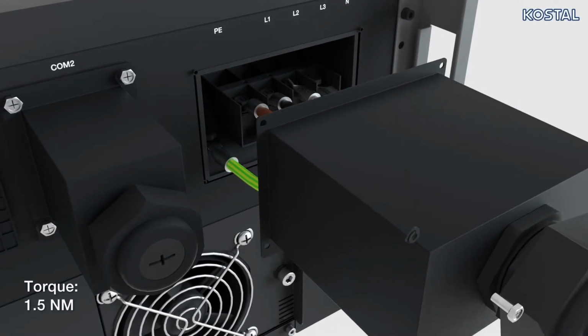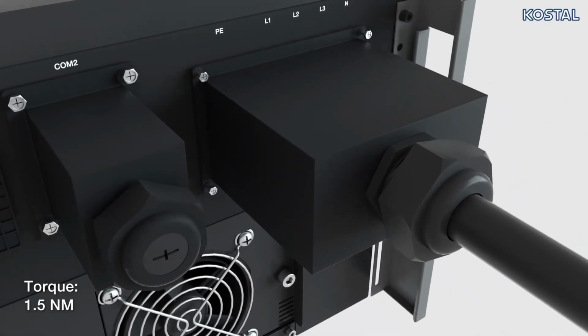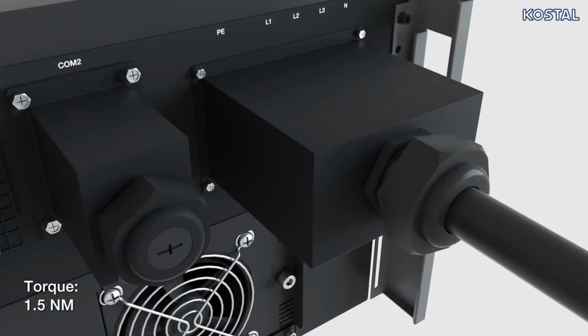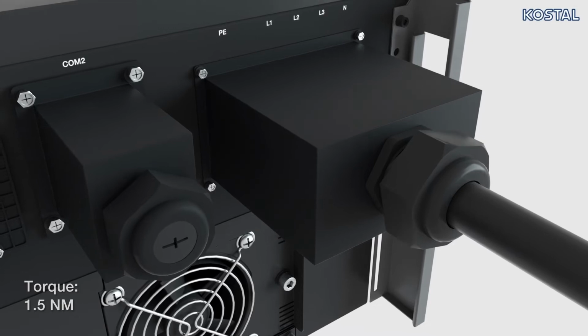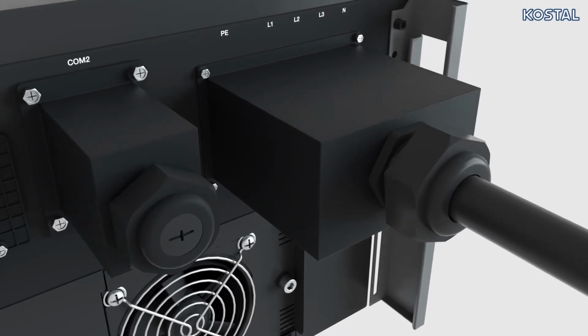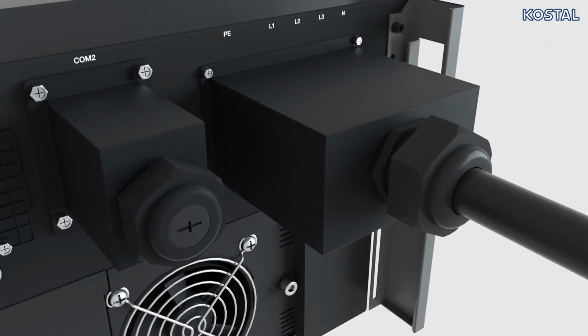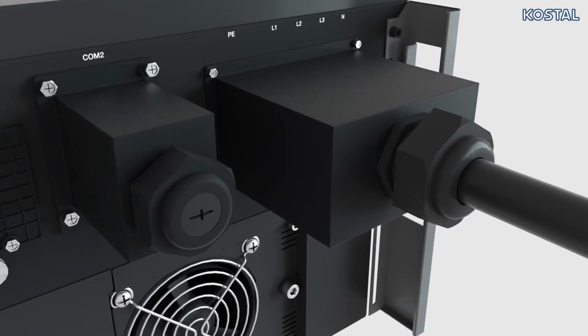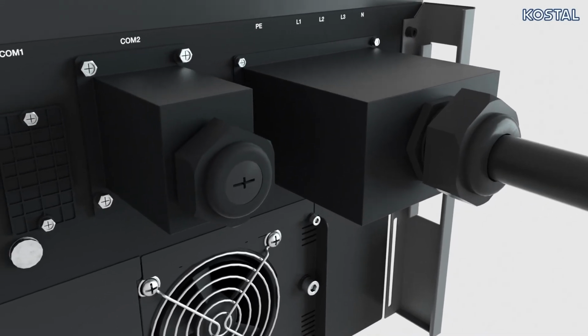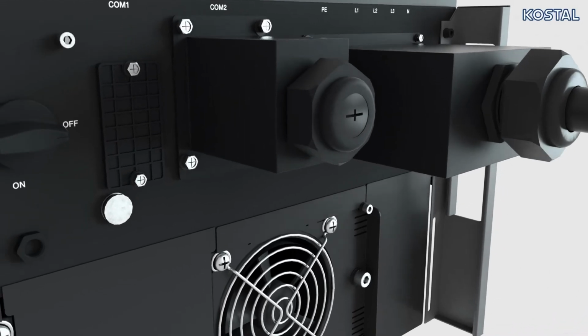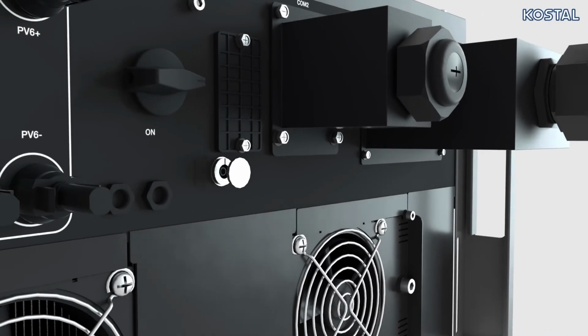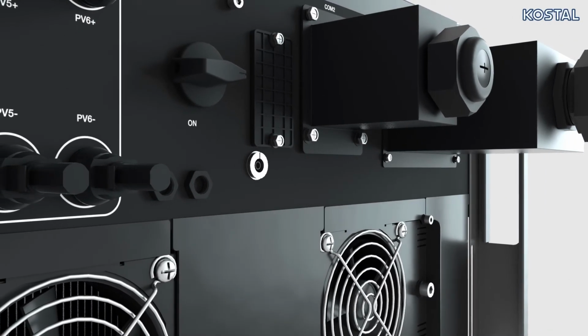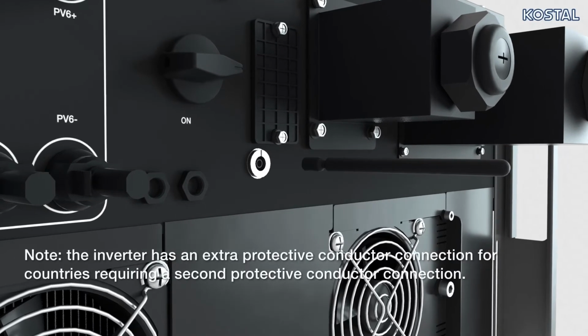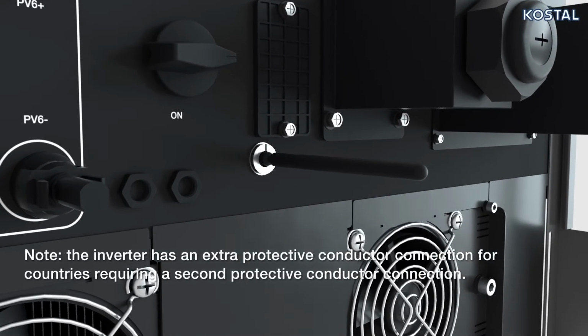Reattach the connection cover on the AC connection and screw it down. Screw the sealing ring back down with the cable on the inverter. The AC cable is now connected and can now be properly laid in the sub-distribution. Now remove the protective cap from the connection thread and screw the Wi-Fi antenna provided onto the connector bolt.